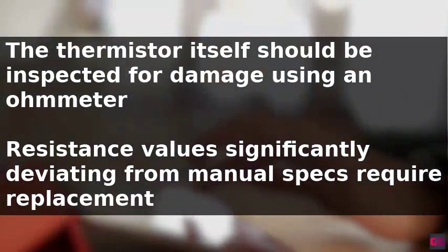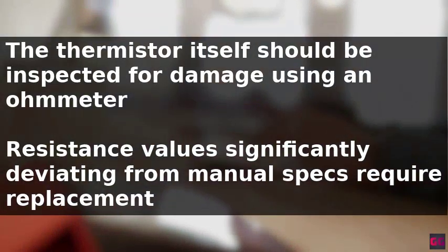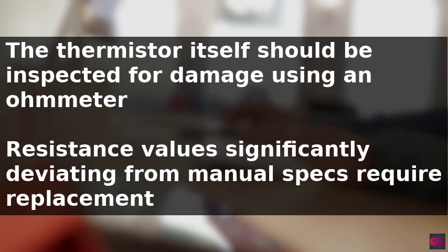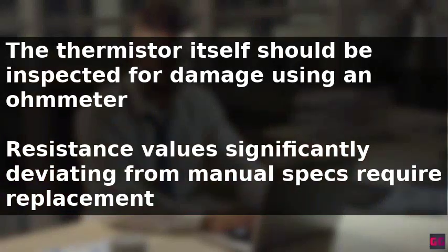If the wiring is not the issue, the thermistor itself should be inspected for damage. Using an ohm meter to check the thermistor's resistance is crucial, and if the values significantly deviate from the manual specifications, the thermistor should be replaced.